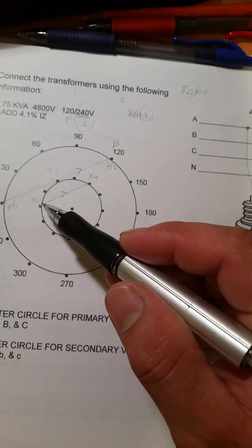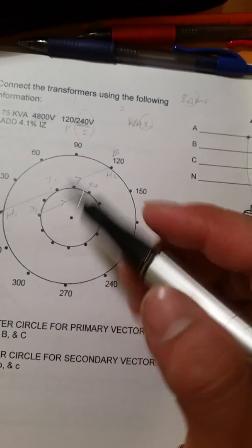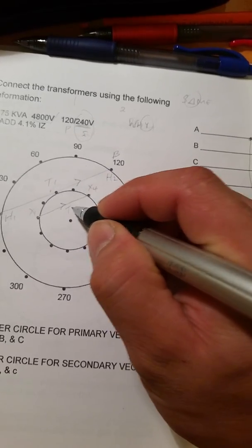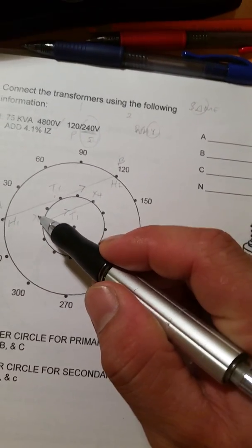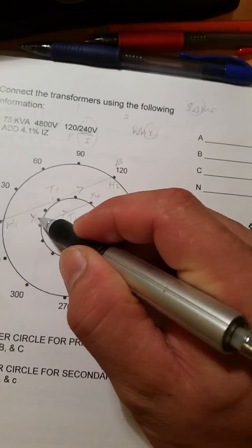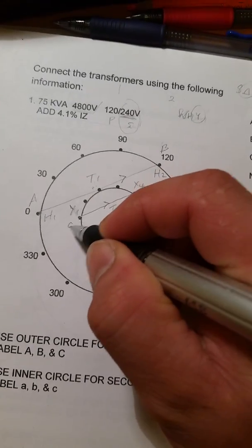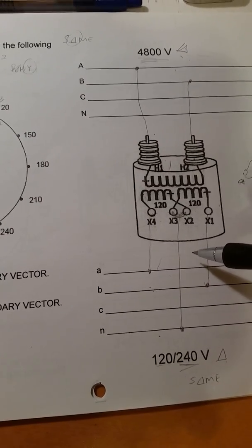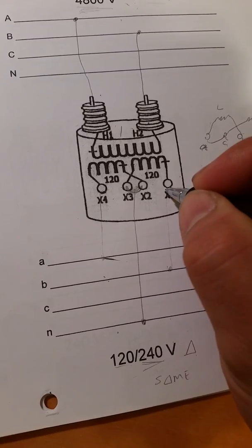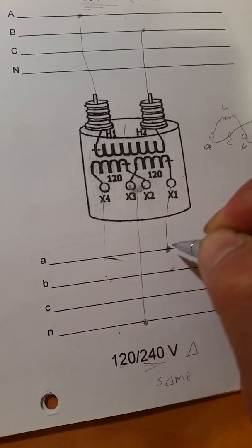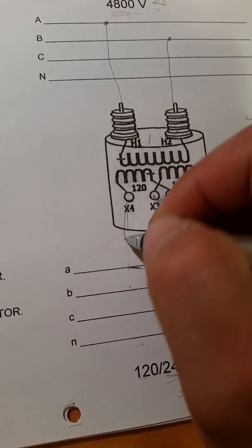Vectoring helps you kind of learn how to hook it up too. So that's transformer 1. This is also transformer 1 secondary side, right? So X1 is where it's going in, right? Oh yeah, there's your A phase and B phase. Oh, I hooked this up wrong. It's going in that way, and it's coming out of B phase. See that?